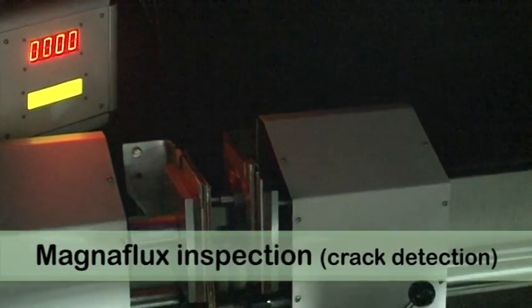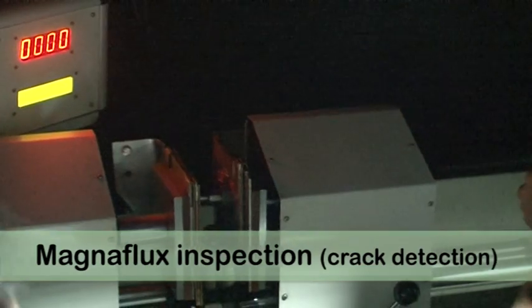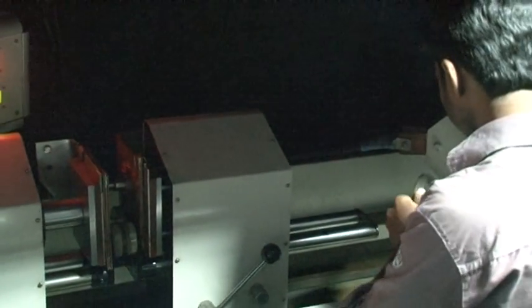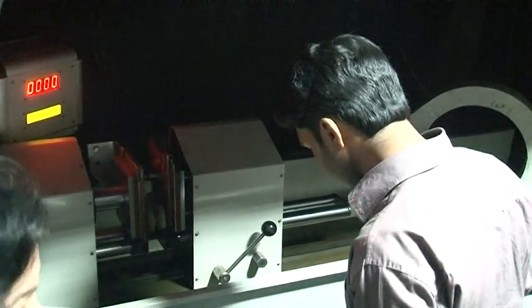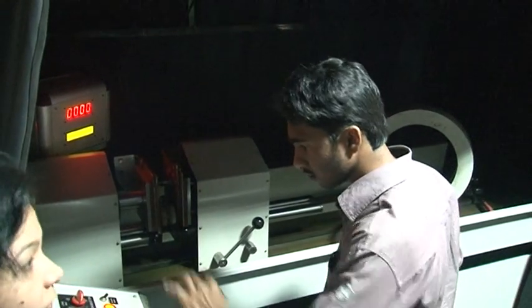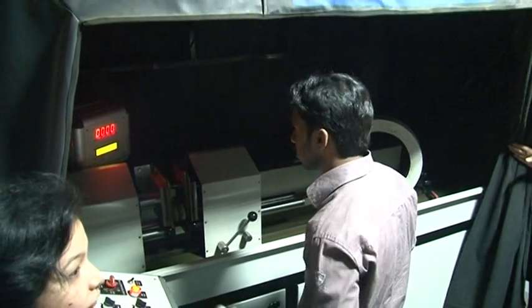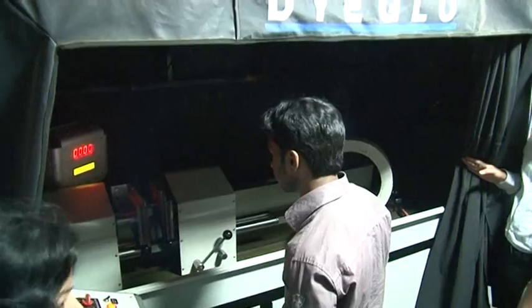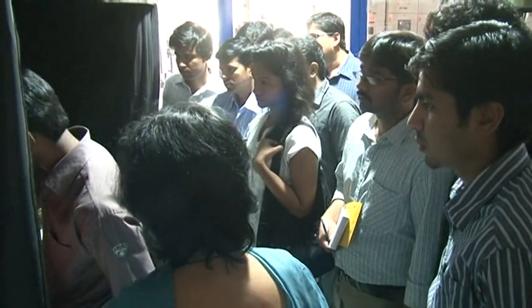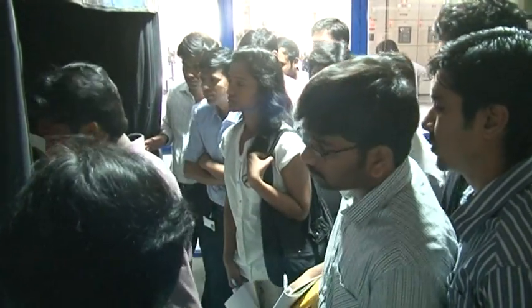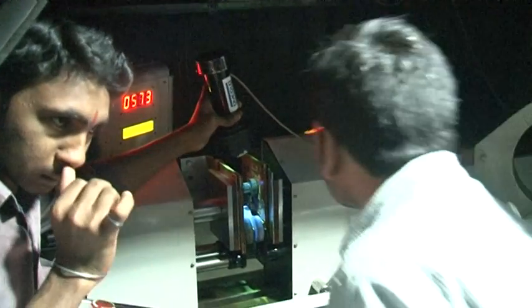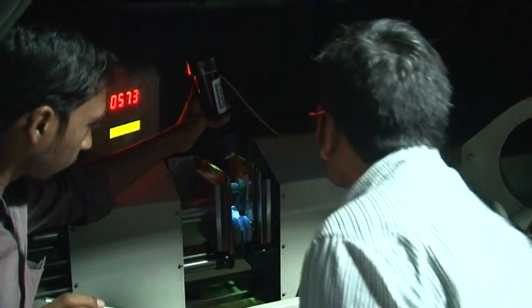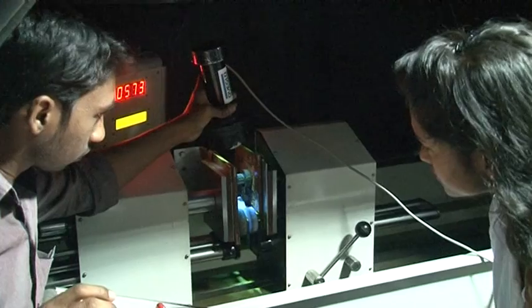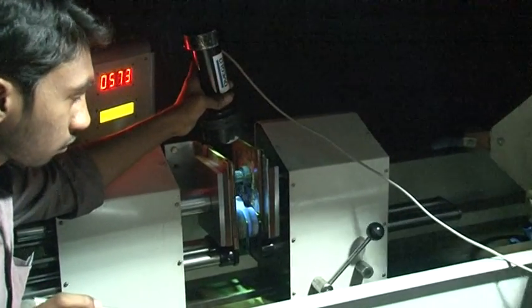Magnetic particle test. External cracks in ferromagnetic materials like steel or iron casting can be checked. These are surface defects. The job is held between copper pads on the jaw of the table. It is held tight. A current of 1000 to 2000 ampere is passed for a fraction of a second. As a result of the passage of current, the part gets magnetized.